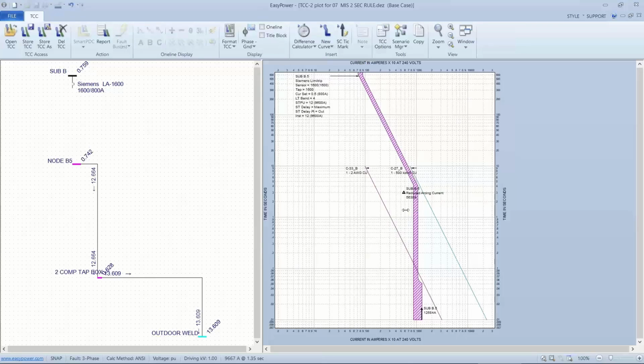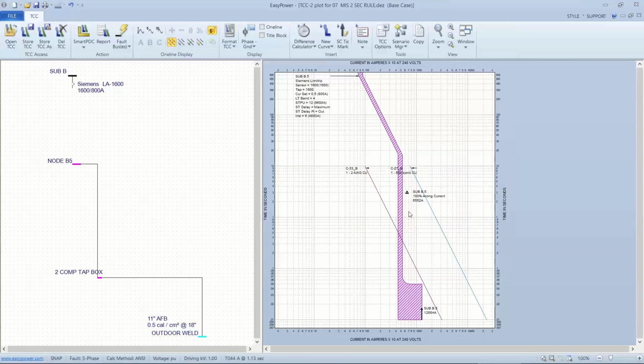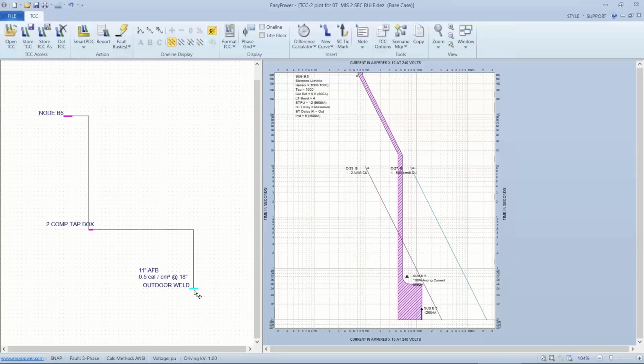So if I left click and drag, let's look at my incident energy over here. 127 calories the way things are set up. If I readjust my breaker so that the arcing current falls in the instantaneous band of the breaker, now I get a half calorie exposure. So my problem is that because we were artificially limiting the time to 2 seconds, we obscured the fact that this is miscoordinated. It really wasn't all that obscured because we still had high incident energy and something should have rung a bell. So again, if you're going to use the 2 second rule, which is limiting calculation time to 2 seconds, do it after you've done coordination because you don't want to obscure what's going on.